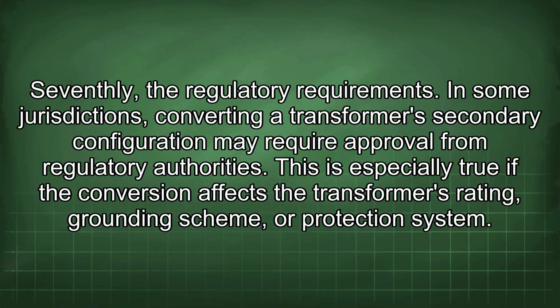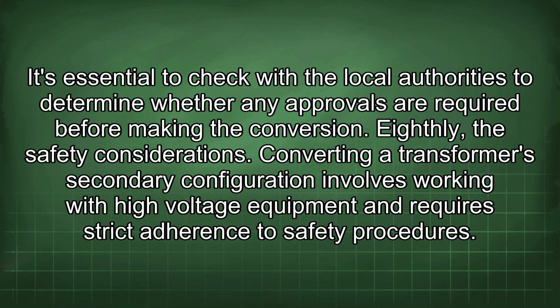Seventhly, the regulatory requirements. In some jurisdictions, converting a transformer's secondary configuration may require approval from regulatory authorities. This is especially true if the conversion affects the transformer's rating, grounding scheme, or protection system. It is essential to check with the local authorities to determine whether any approvals are required before making the conversion.